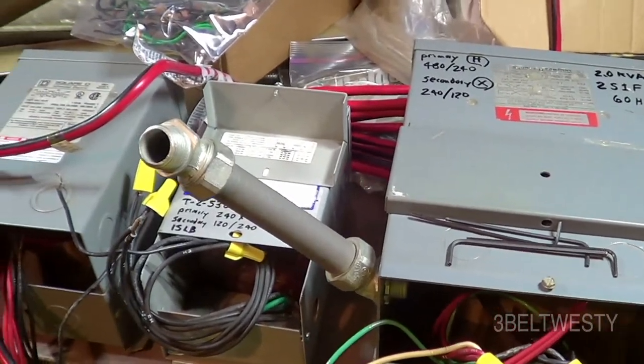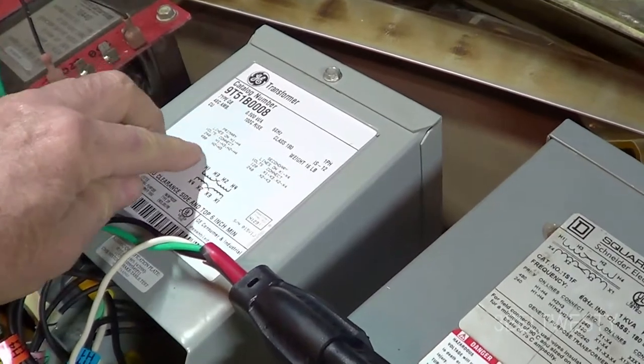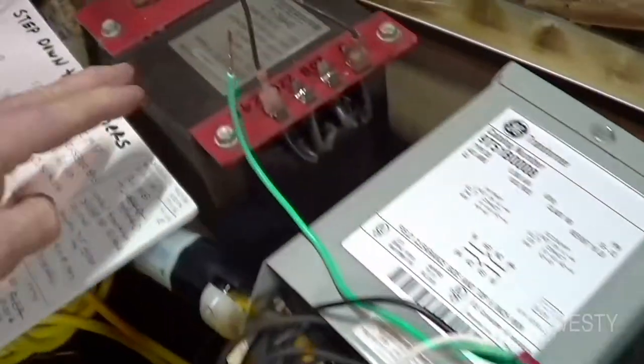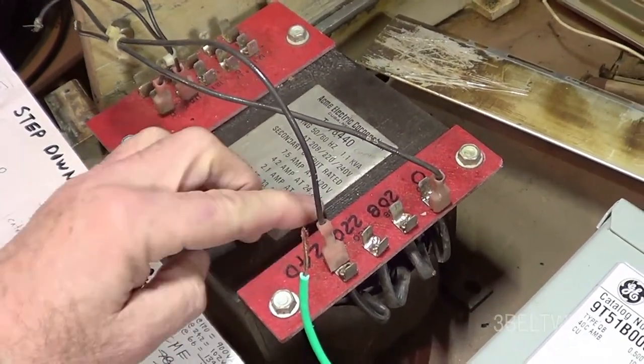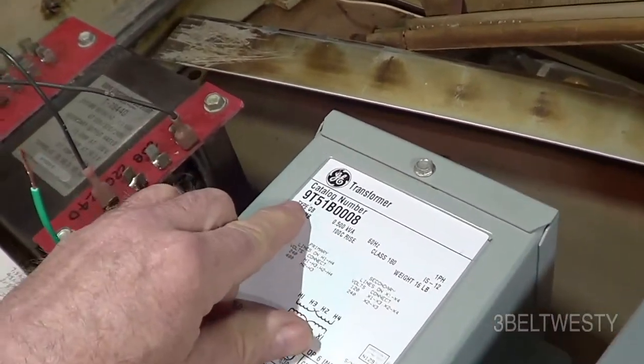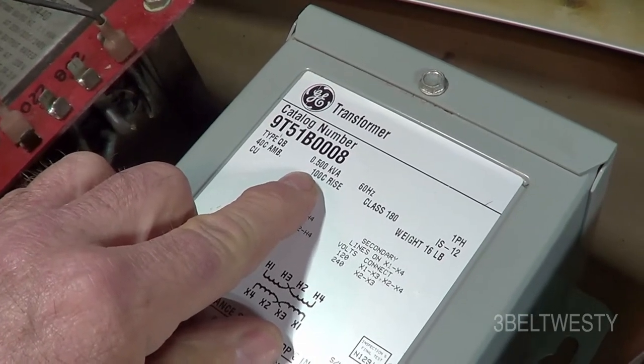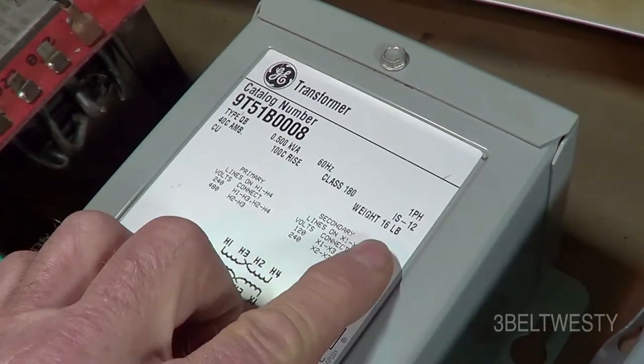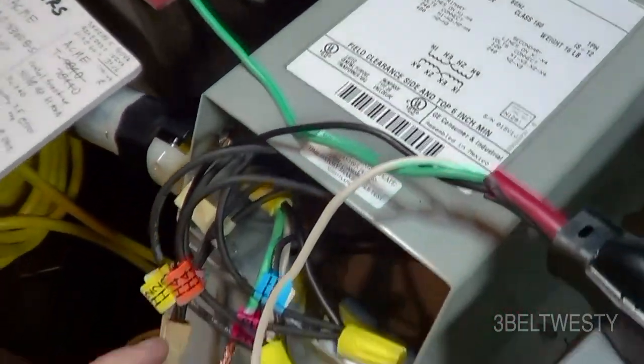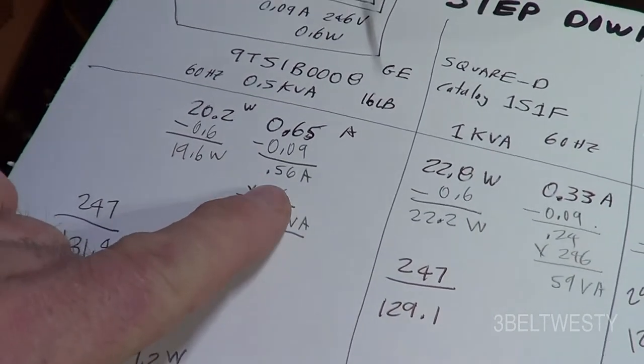On the lab bench I've got five step-down transformers and I'm looking at the core loss. Most of these can have inputs of either 240 or 480. These are all outdoor type 3R. This first one is a GE unit — a 9T51B0008, 500 VA (0.5 kVA), 60 Hz, class 180, 16 pounds. It's wired 240 in, 120 out, and has a core loss of 19.6 watts.